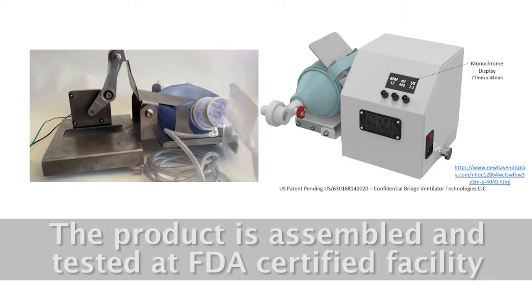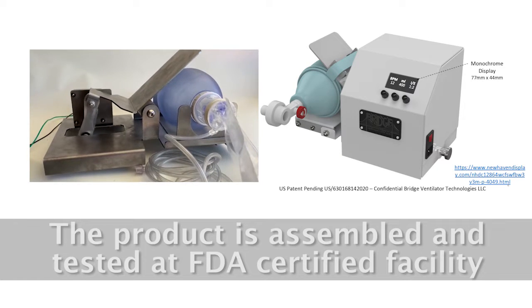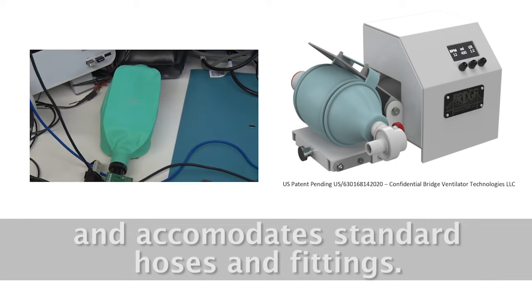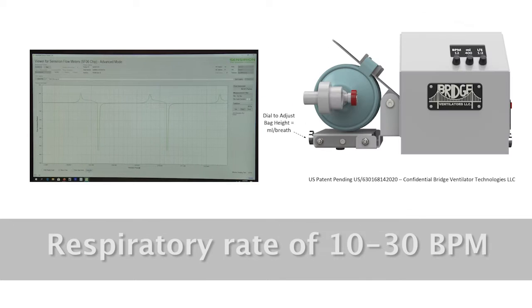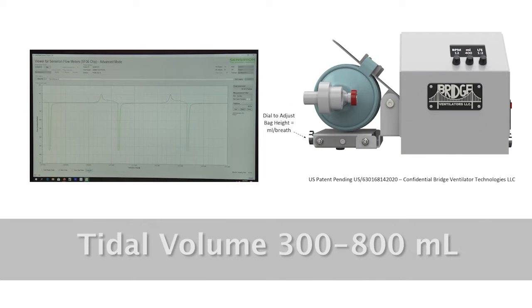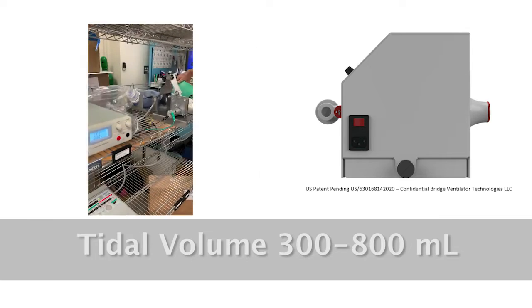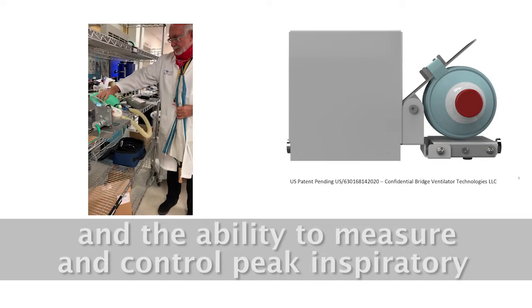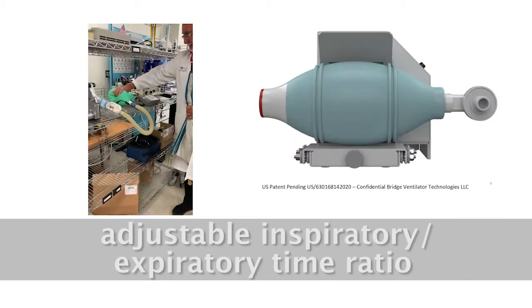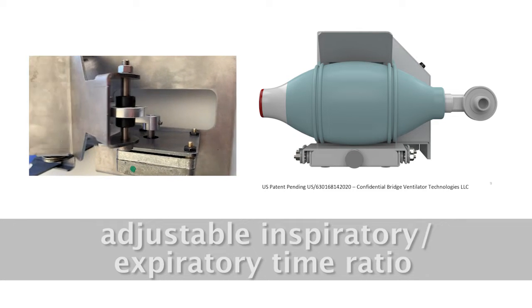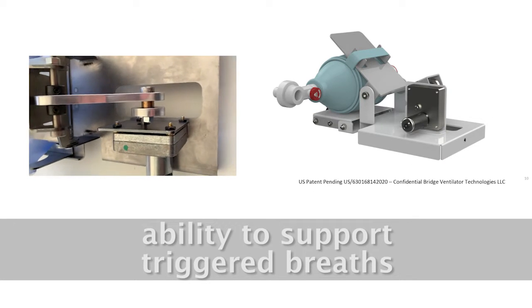The product is assembled and tested at an FDA certified facility. It accommodates standard hoses and fittings, a respiratory rate of 10 to 30 breaths per minute, a tidal volume of 300 to 800 ml, and the ability to measure and control peak inspiratory pressure, adjustable inspiratory to expiratory time ratio, and the ability to support triggered breaths.